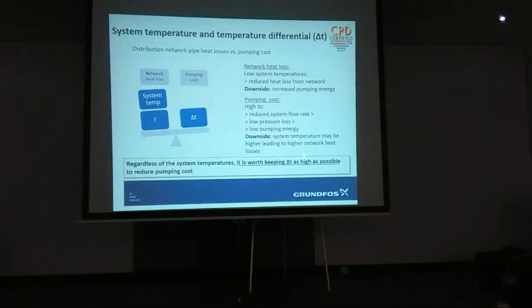But if you keep the delta T as high as possible, you reduce your flow rate, reduce your resistance, and therefore reduce your pumping cost. It's a smaller pump, which for the likes of me and Nigel is not very good, is it, Nigel? No. You want bigger pumps. And if I was paid on commission, you want huge pumps. But smaller pumps make this easier to control. If you oversize on a district energy system, you won't get your return temperatures right. When there's low demand, you will have loads of problems.